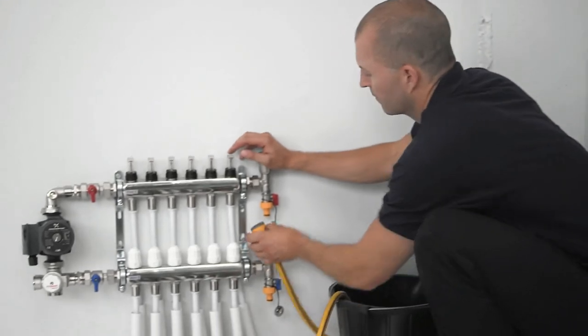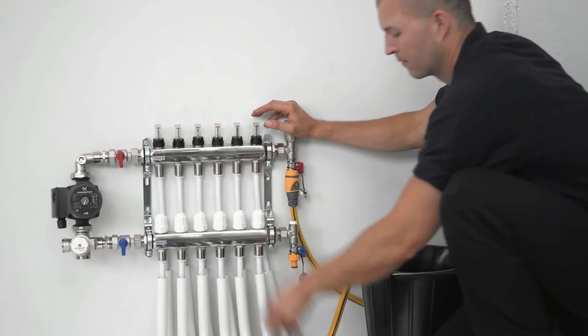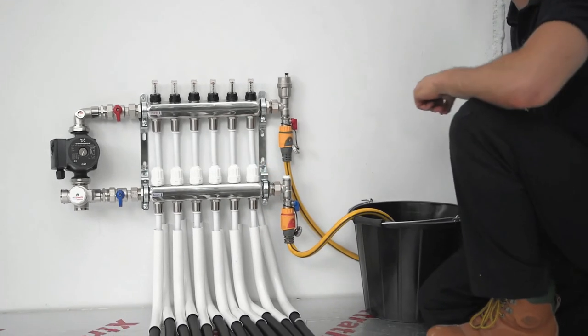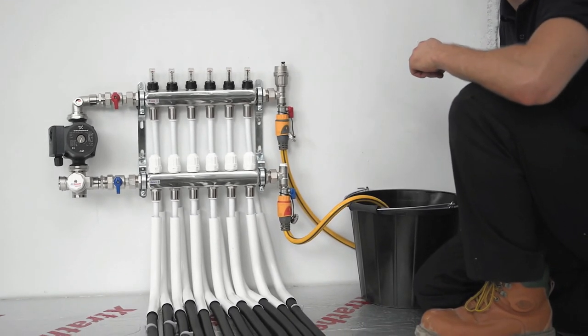If the UFH is being installed when there is a possibility of freezing conditions, suitable antifreeze should be added to protect the pipework. The system will need to be flushed out and refilled prior to operation.